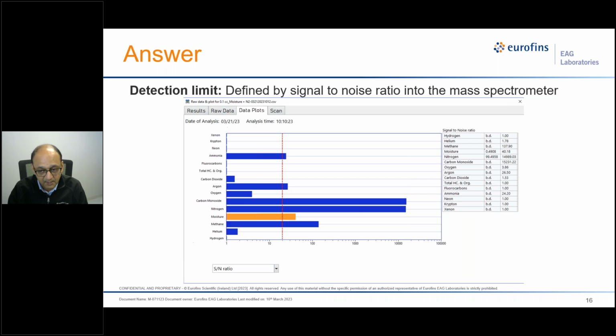Another challenge could be, because it is all controlled by the background signal, that our mass spec has an inbuilt memory effect for nitrogen. Nitrogen is always being introduced into the mass spec, and even the atmosphere has 78% nitrogen. So nitrogen and oxygen have some inbuilt background generated in the mass spec. If we have to measure nitrogen at less than 100 ppm or 50 ppm, we have to season our mass spec for that kind of environment. We have to get ready for that. But in general, for other gases, we have successfully achieved a 50 ppm detection limit for most of the gases.